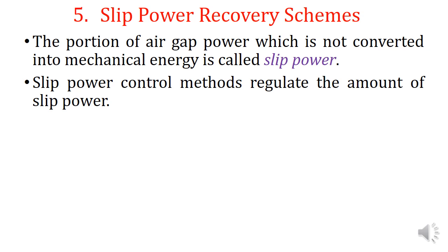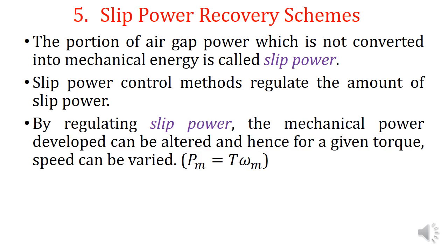The slip power control methods regulate the amount of slip power — how much slip power should be fed back to the source is controlled. By regulating the slip power, the mechanical power developed can be altered, and hence for a given torque, speed can be varied.